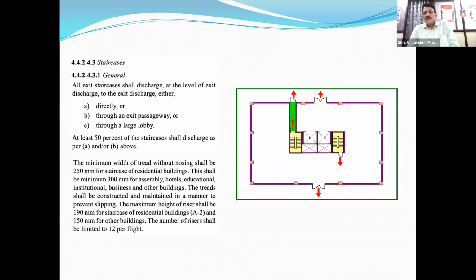Then there are other important things that are prescribed, such as the width of the tread and the riser. These also play an important role in evacuation, because if there is any non-uniformity between the flights in a staircase, it will lead to people tumbling on the staircase. And if it is too steep or too low, then also it will not be very good for evacuation purposes. So NBC has prescribed the width of the tread and the riser. They also play an important role for external staircases and for internal staircases. It is given in the NBC.